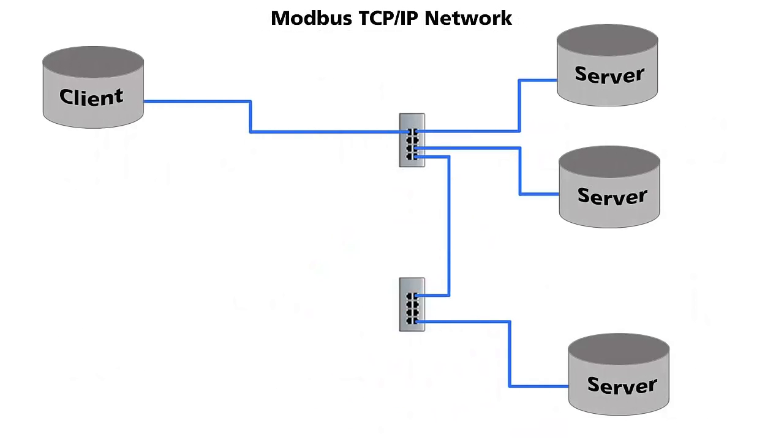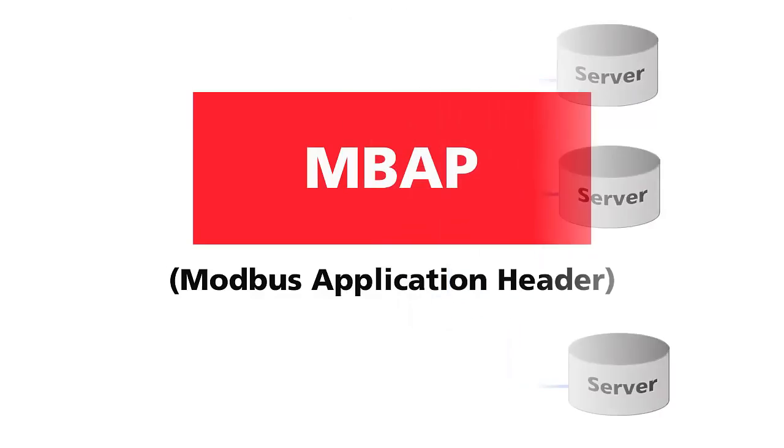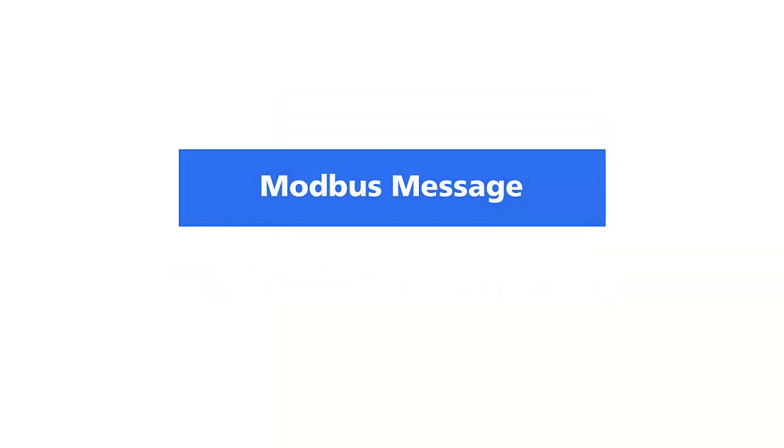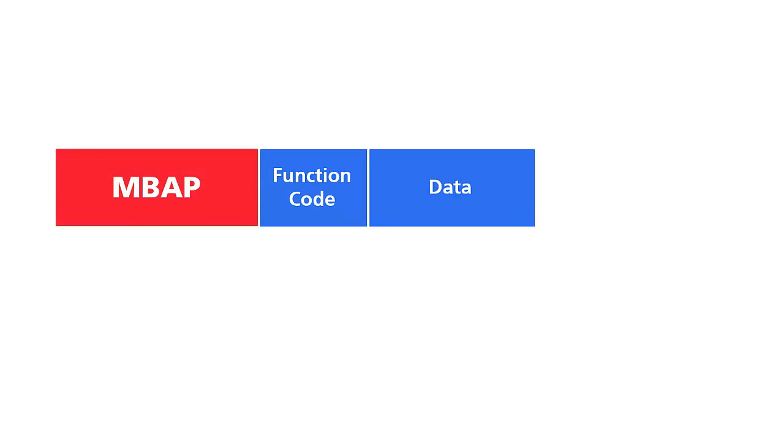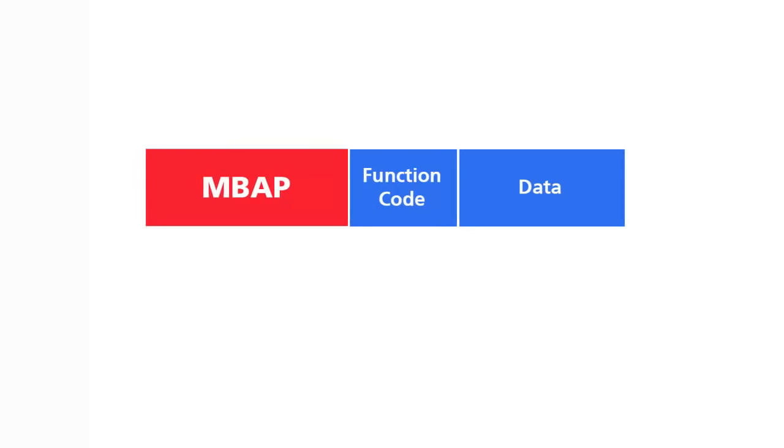Modbus over Ethernet operates exactly like it sounds. Modbus devices using regular Ethernet cables and switches to communicate with each other. The big difference with Modbus TCP IP is that an MBAP header, or Modbus Application header, is added to the start of each message. The slave ID at the beginning of the message is removed, as well as the cyclic redundancy check at the end. The MBAP header contains all the identifying information needed to route the data to the address device.